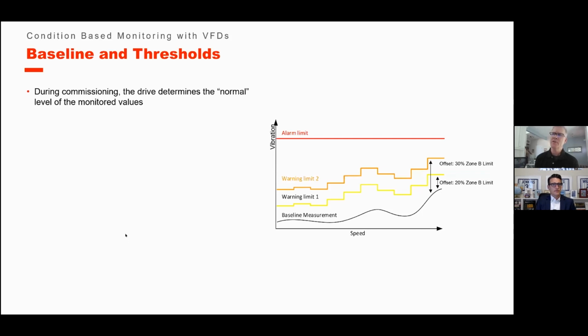During commissioning, the drive determines the normal level of monitored values. So as you commission the drive, start it up, and plug in everything you need to get it running on the application, once the application is running, those regular normal values will be determined at that point. You've got a well-running machine, and that's where you want to measure those baselines so you can monitor against them. The speed range at that point is divided into 20 points. So how this actually works is, on a typical machine, we may run through a speed range, let's say 500 to 1,000 RPM in the process. We take that 500 to 1,000 RPM and divide it into 20 data points.